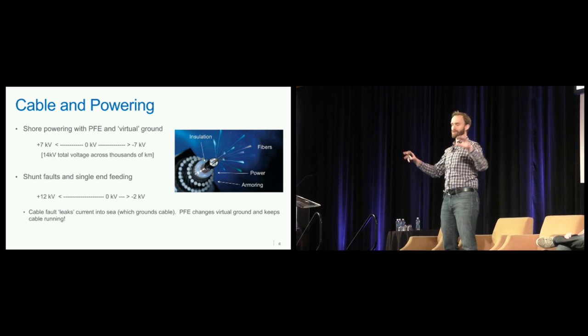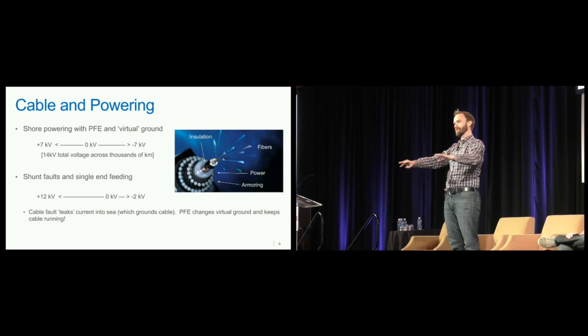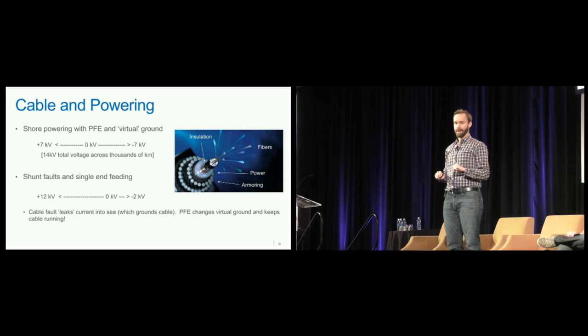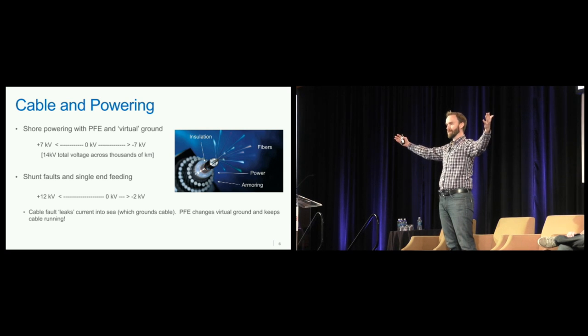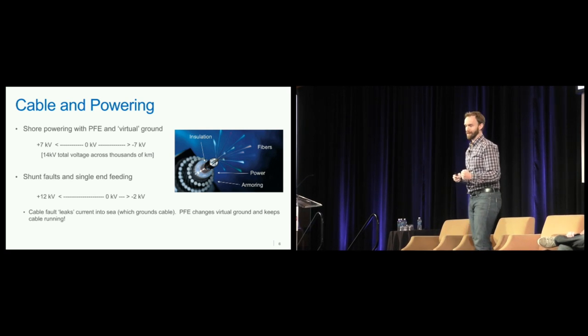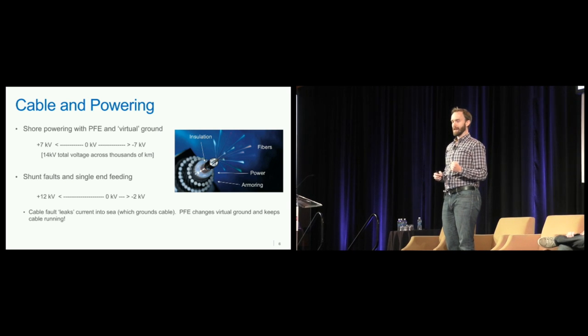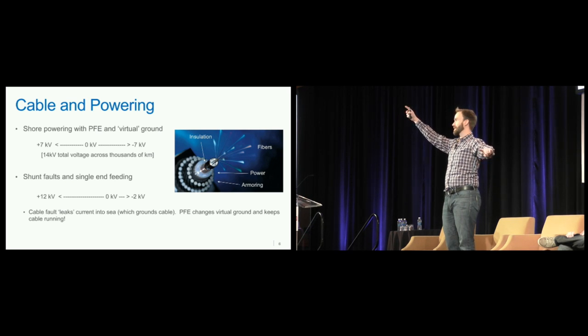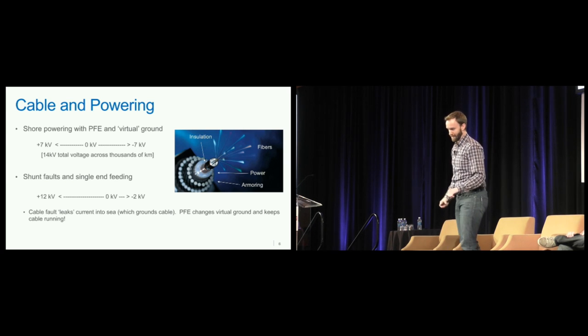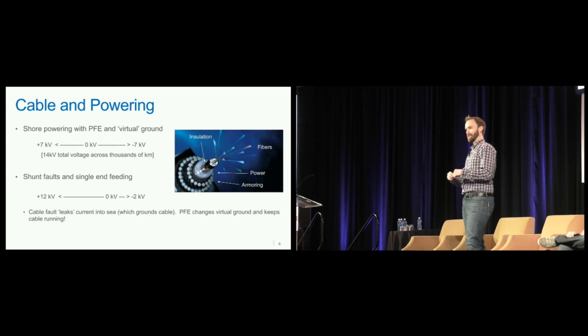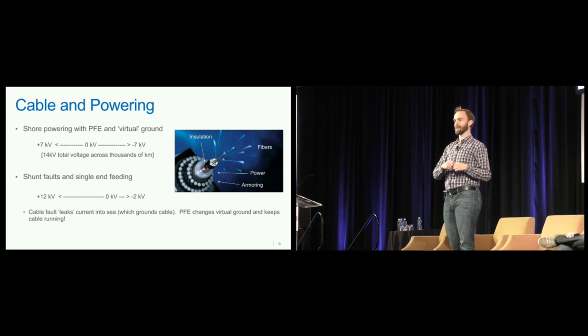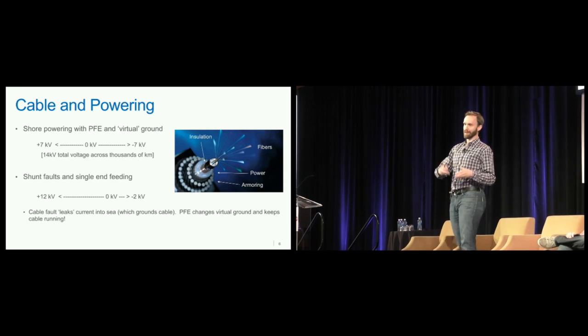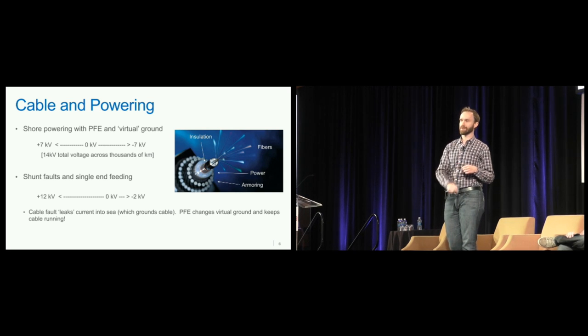The power feed equipment is really cool. Imagine a cable 12,000 kilometers across the ocean — all you have is equipment on the ends to power it. In this example, I've shown a 14 kilovolt PFE. You set the PFE to plus 7 kilovolts on one side and minus 7 on the other, and somewhere in the middle there's a virtual ground at zero. The 14 kilovolts runs across the copper — just a few milliamps — and it powers all the active components of the cable, amplifying the light every 60 to 80 kilometers.